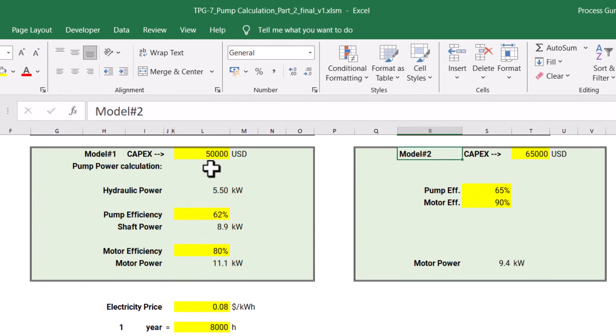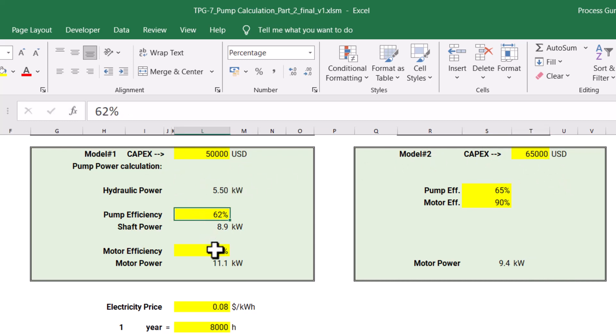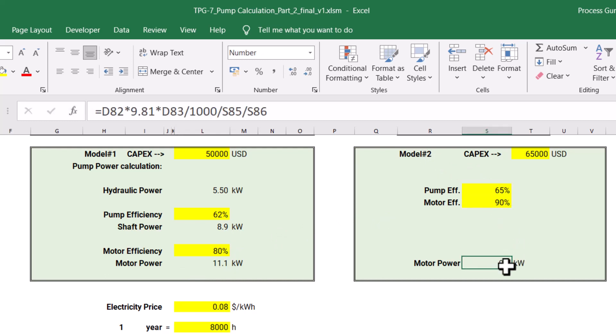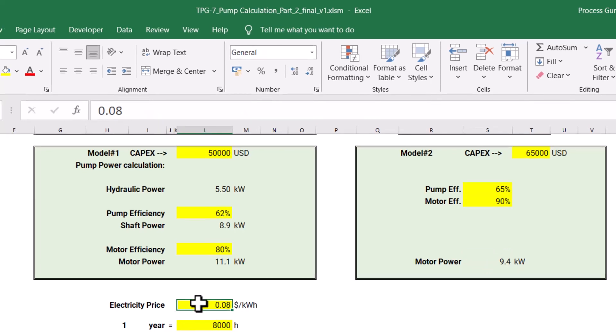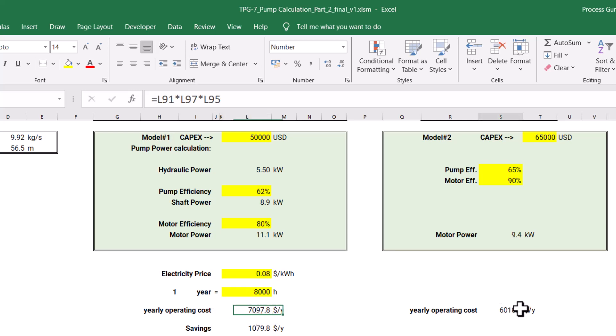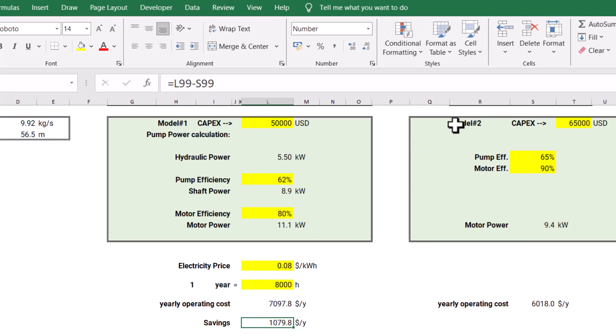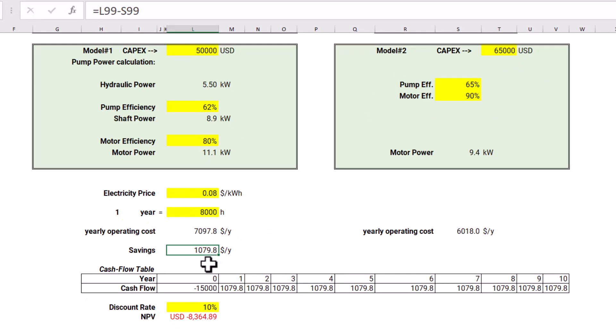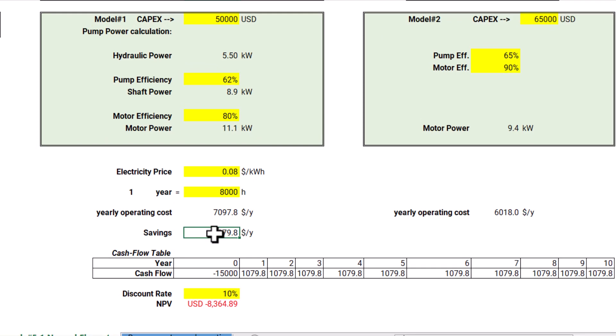In Excel, I have highlighted the information for model one and model two. Model one has a CAPEX of $50,000 and model two is $65,000. For model one, given its pump and motor efficiencies, the motor power consumption is calculated. For model two, with its higher efficiencies, the motor power comes out to 9.4 kilowatts. With an electricity price of 8 cents per kilowatt-hour, the yearly operating cost for model one is about $7,097.8 per year. Model two's yearly cost is lower, and the corresponding saving is $1,079.8 per year.